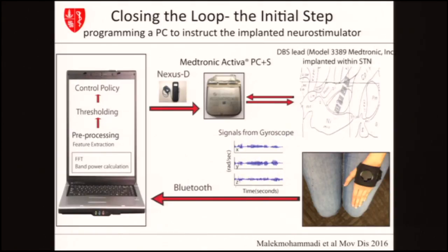So we did a collaboration with them, and we used this smartwatch and had the patient just sitting with the other side on so that tremor wouldn't interfere from the other side, and just had it resting on their leg so that we could measure tremor from the leg and the hand. And this here is the wearable sensor, and you can see the angular velocity of tremor was picked up by the PC. We did an FFT of the tremor power, did a calibration, and then asked the stimulator to sense tremor.